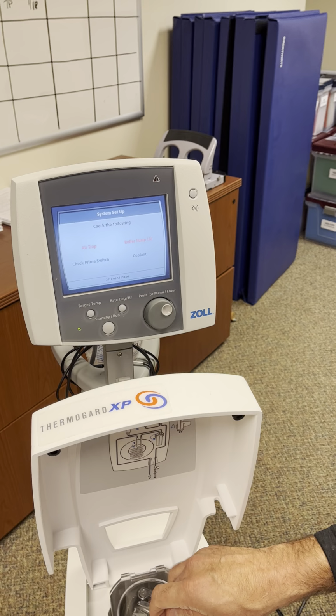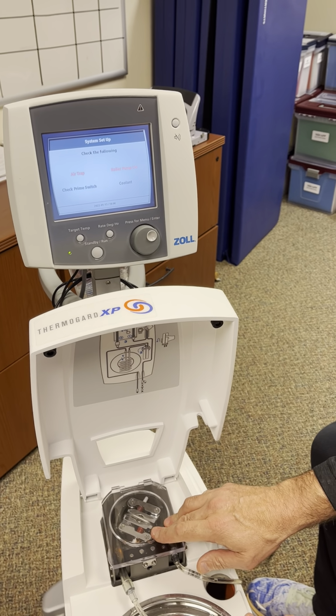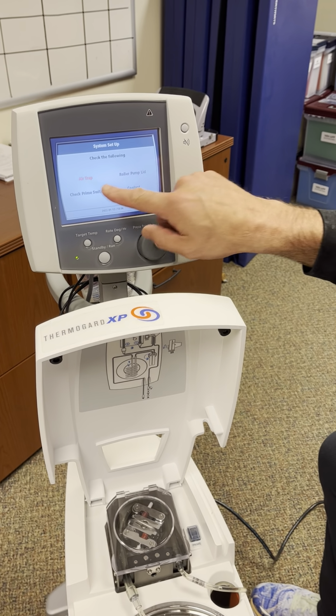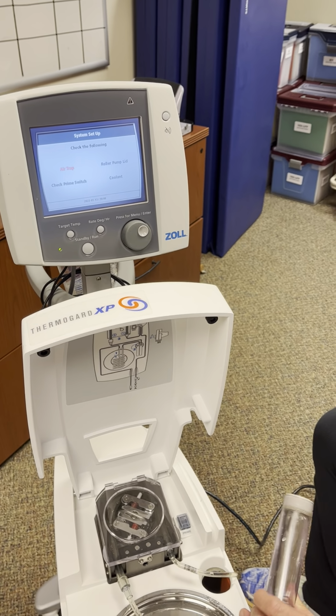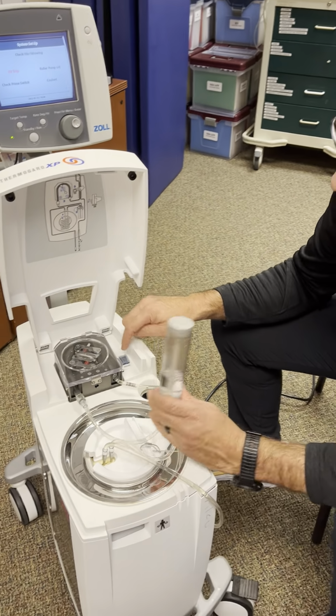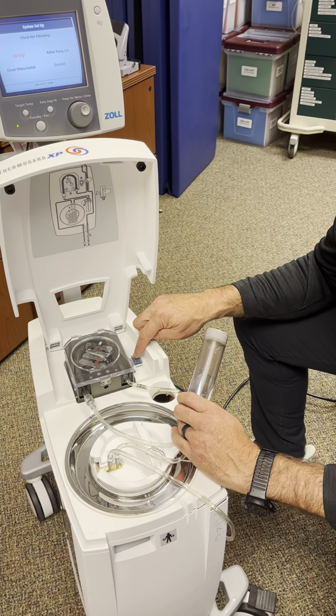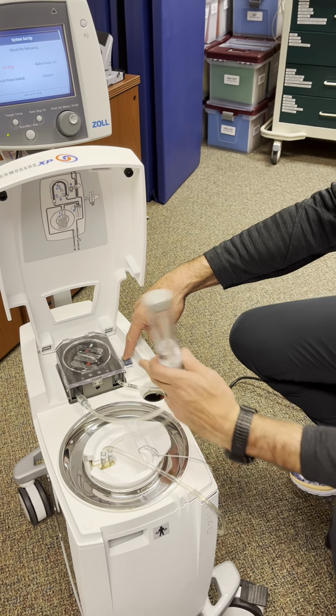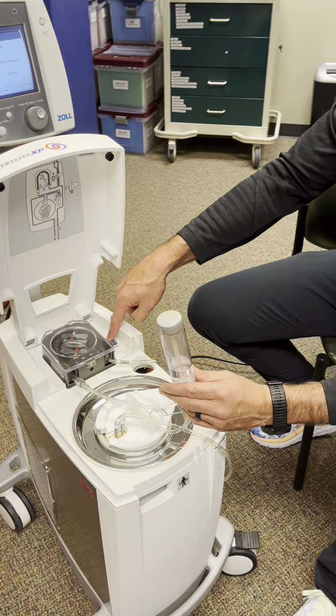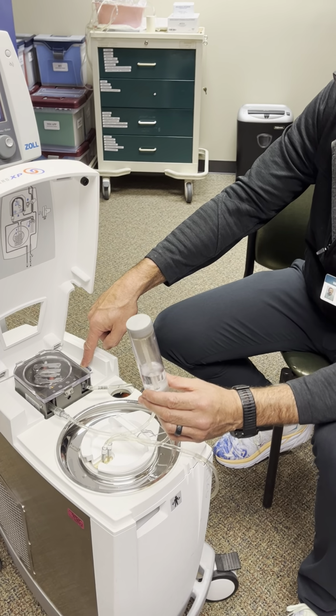We're going to lower the lid on our pump. The alarm goes off, and then you'll see that the air trap needs to be primed. In order to prime the air trap, you have a prime button here. Finger on it, you'll see the pump light up, and it takes a few seconds for it to engage.